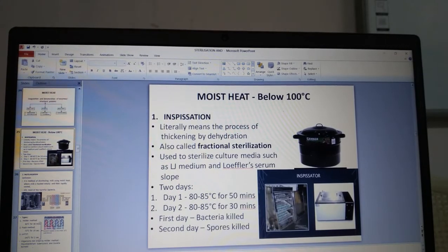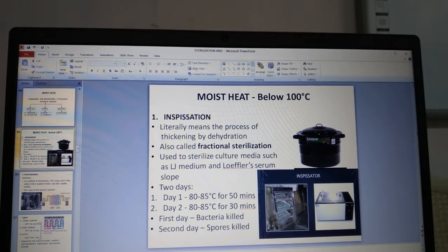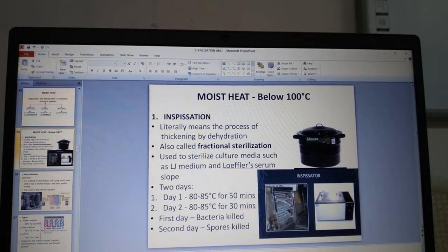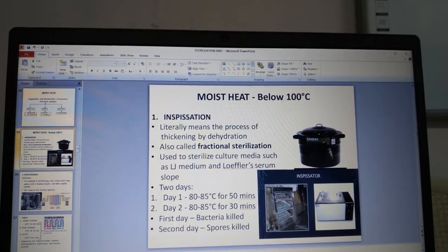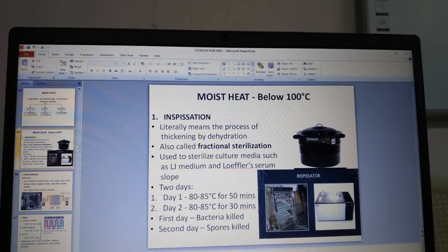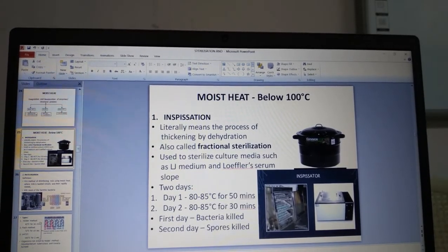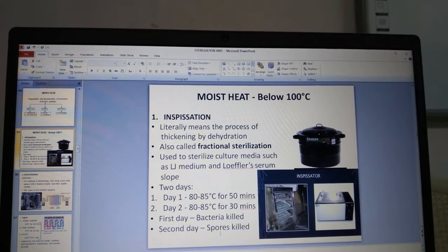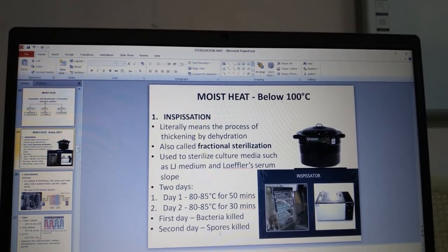Moist heat below 100°C — inspissation. Inspissation literally means the process of thickening by dehydration; it is also called fractional sterilization. It is used to sterilize culture media such as LJ medium and Loeffler's serum slope. The process is done over two days in an inspissator: day 1 at 80–85°C for 50 minutes; day 2 at 80–85°C for 30 minutes. On day 1, bacteria are killed; on day 2, spores germinate in the favorable moist atmosphere and produce vegetative bacteria, which are then killed.